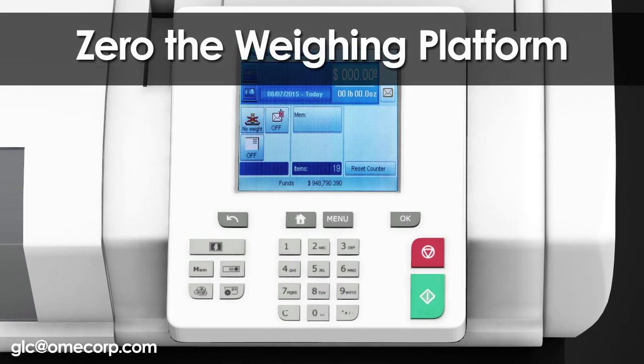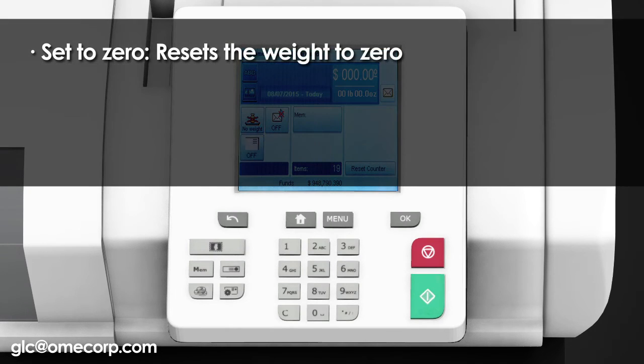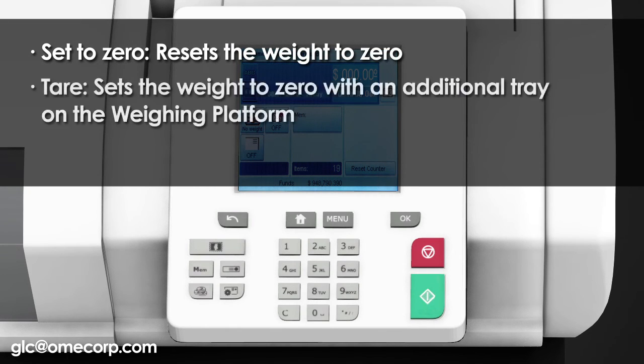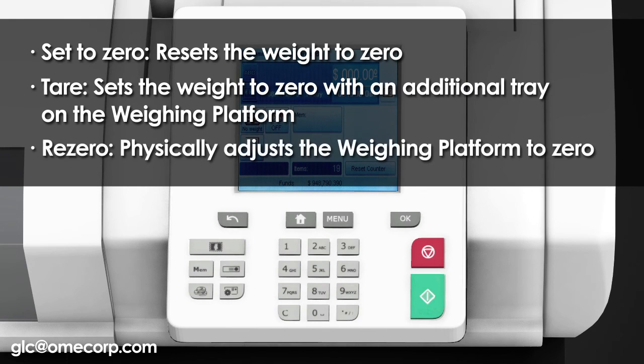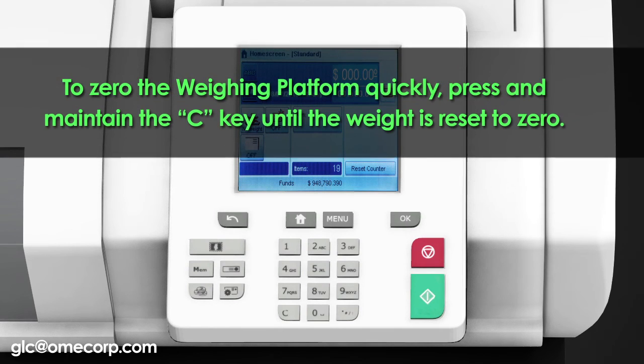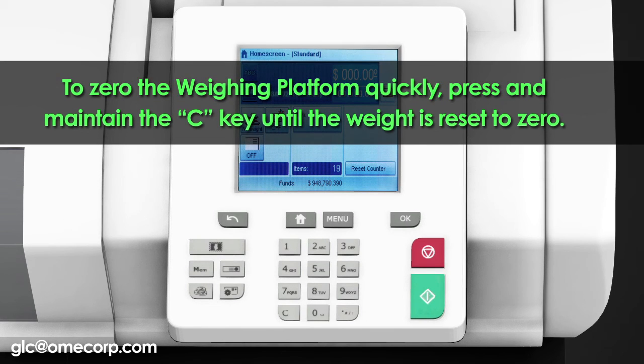Now let's zero weigh the scale. You can reset the weighing platform in the following ways: Set to 0 resets the weight to 0. Tare sets the weight to 0 with an additional tray on the weighing platform. ReZero physically adjusts the weighing platform to 0. Note: to zero the weighing platform quickly, press and hold the C key until the weight resets to 0.